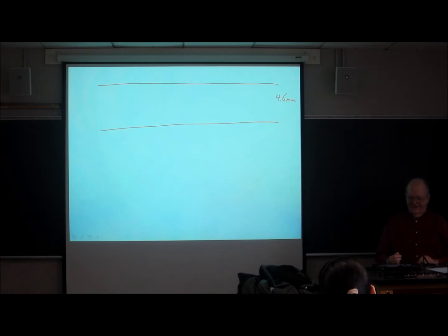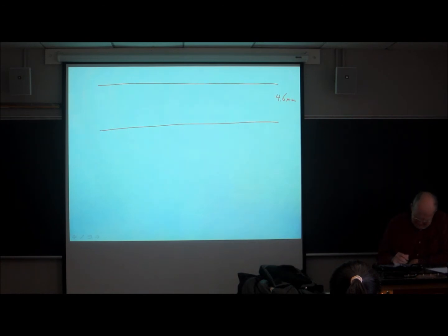Okay, so there's an open tube. We're going to pack particles in this tube. In analytical scale liquid chromatography, this tube typically has dimensions of 4.6 millimeters diameter. And it's packed with particles that are really small compared to the diameter of the column. These days, 5-micron particles are large particles.